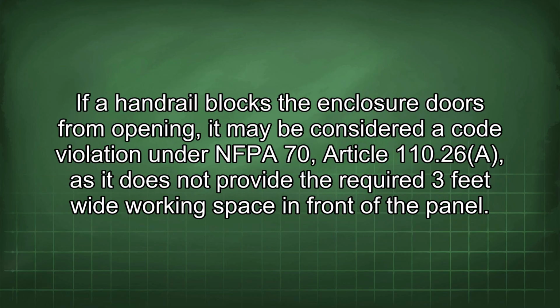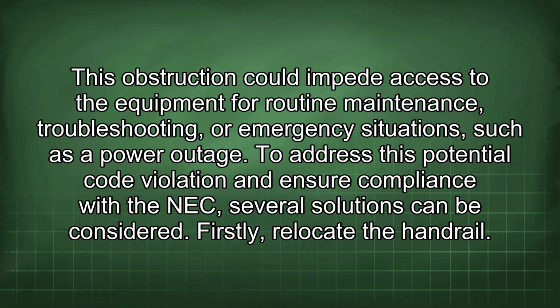If a handrail blocks the enclosure doors from opening, it may be considered a code violation under NFPA 70 Article 110.26a, as it does not provide the required 3 feet wide working space in front of the panel. This obstruction could impede access to the equipment for routine maintenance, troubleshooting, or emergency situations, such as a power outage.